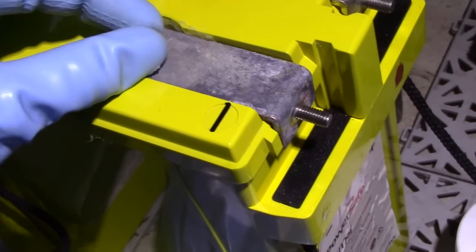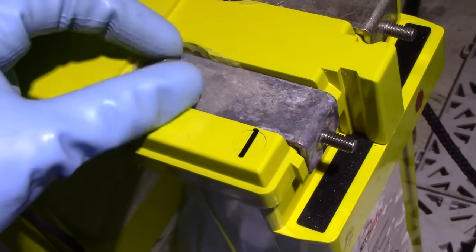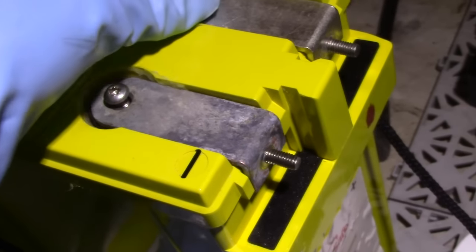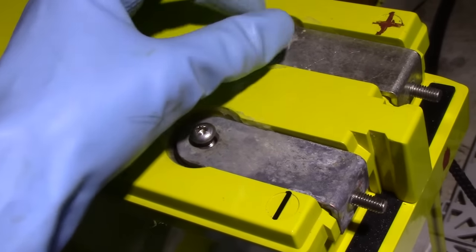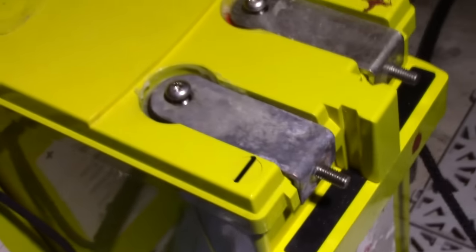The general mechanical build quality of these batteries has been quite good, I must say. They use stainless steel screws for everything, and nuts and bolts, too. Although, sadly, since they have been over-torqued, a lot of them have seen better days.